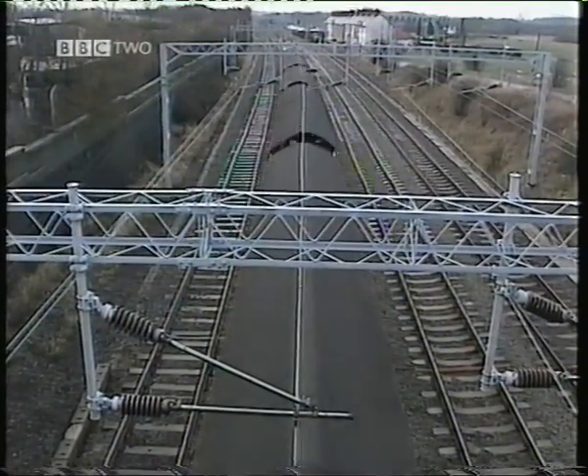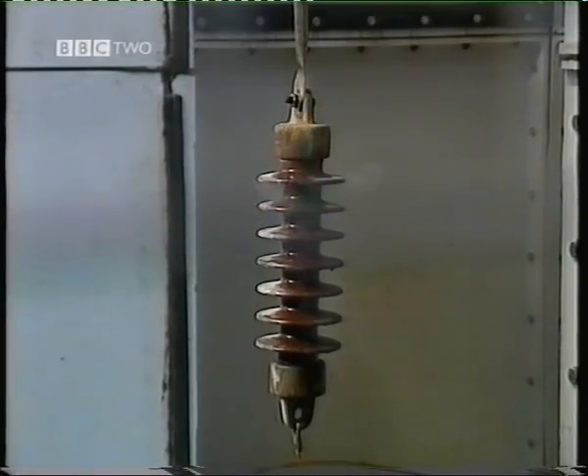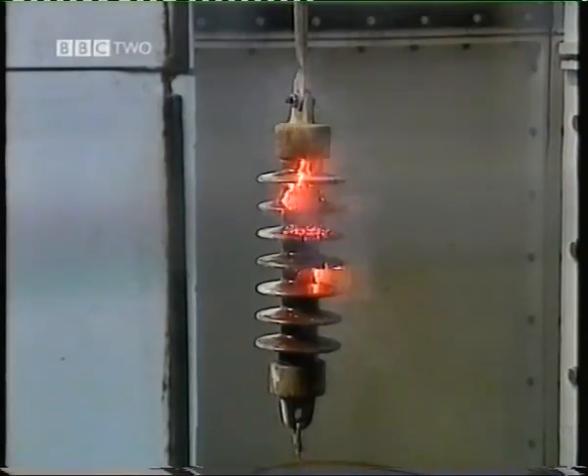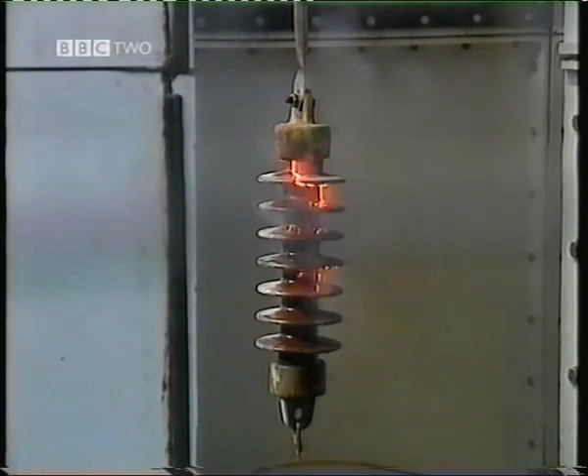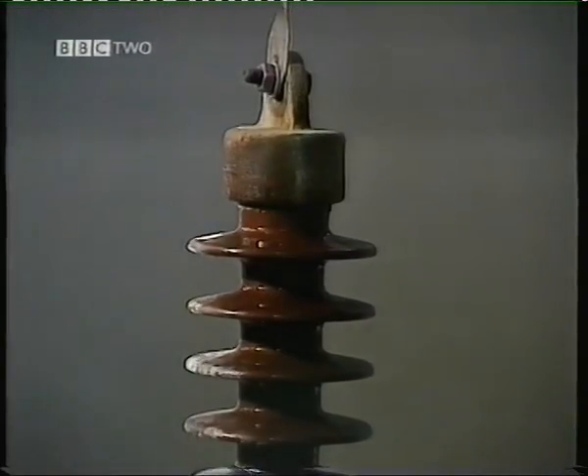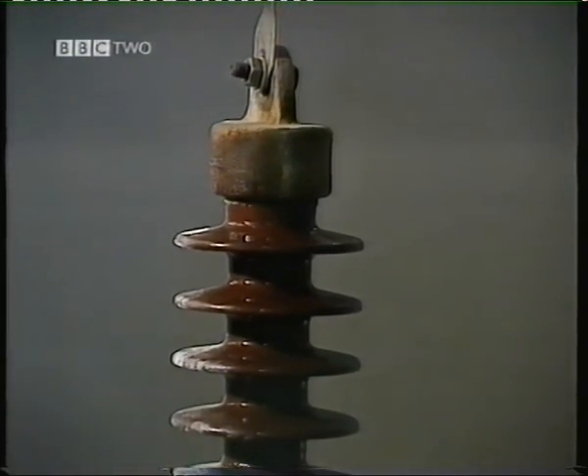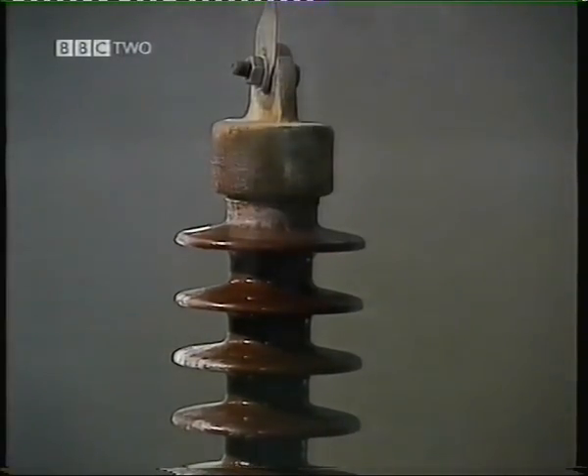Not all materials have the environmental stability of porcelain. Polymeric materials do degrade, either due to sunlight or surface sparking. We test these in the fog chamber by applying salt solution to them, applying 25 kV and leaving the surface arcs to run up and down the surface, and slowly this degrades the polymeric material. These particular insulators that we have chosen have passed all the salt fog tests that we've done on them.